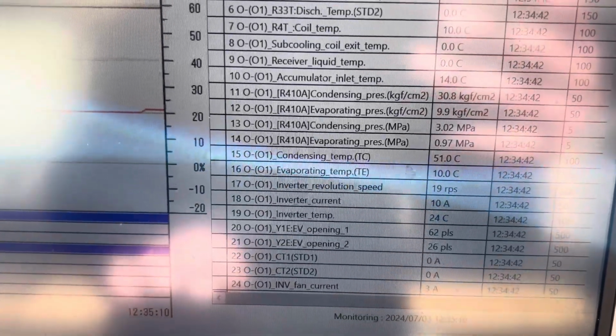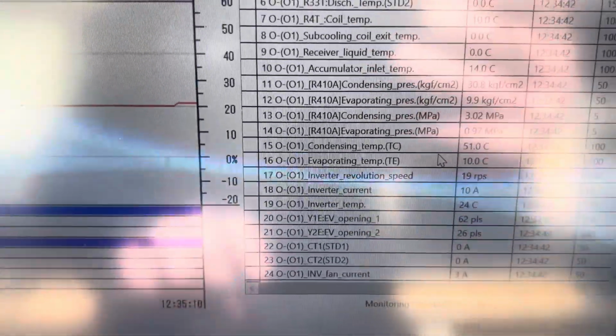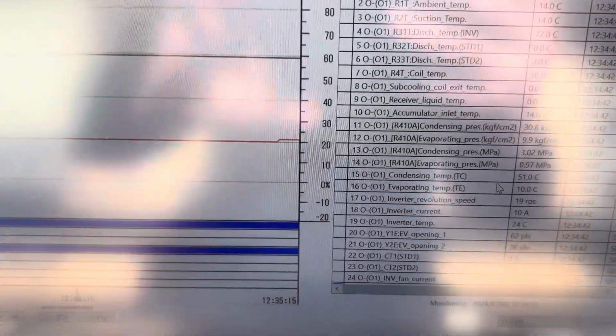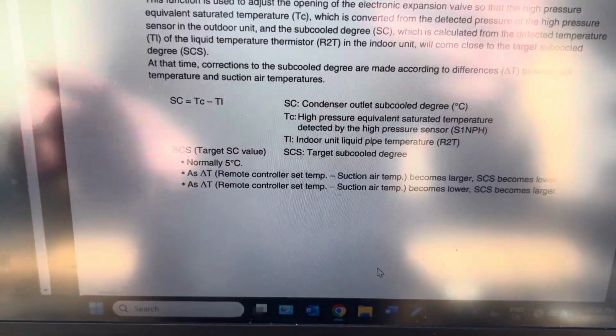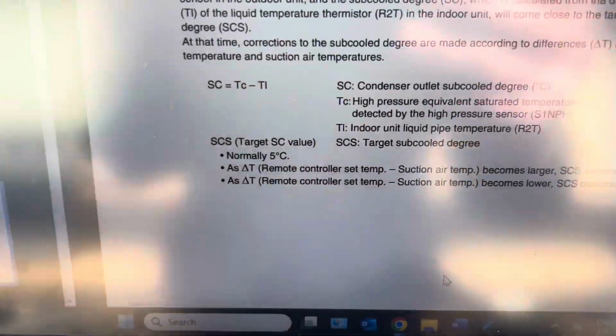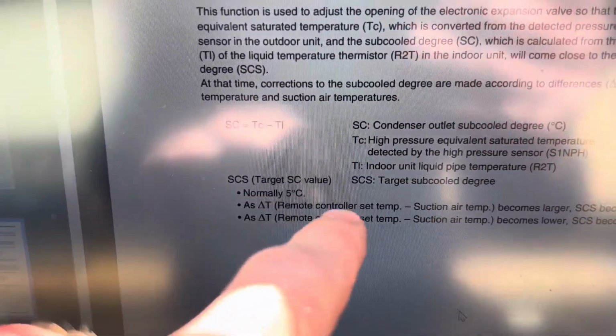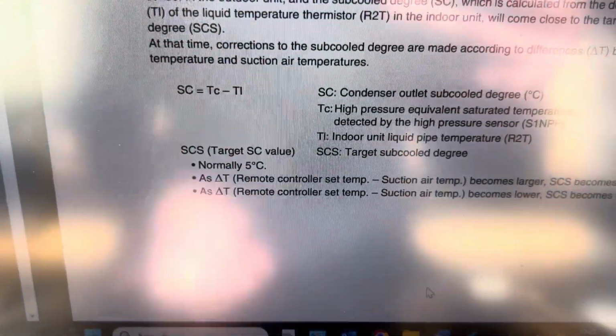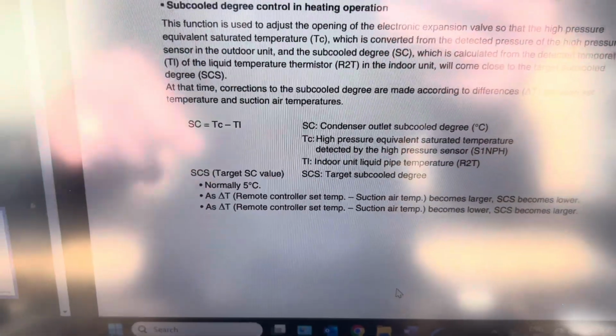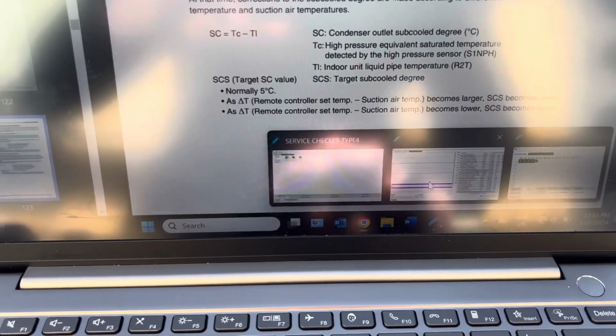So where are we? So we're sitting about 9K subcooling on this unit, right? So these ones are looking for 5K subcool. Actually, I'll show you. So this is just in the manual for this particular unit, but basically you can see here. So that's what it's looking at to get the subcooling number, and that's to say normally 5 degrees, right? But what ends up happening is that LEV will keep opening, pretty much trying to get, let me scroll all back down again.